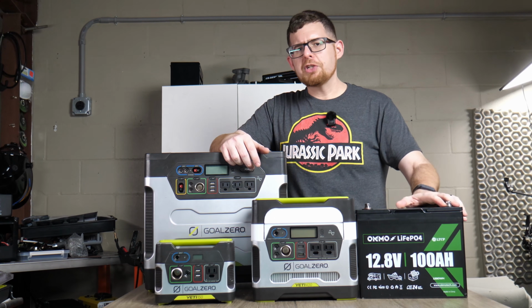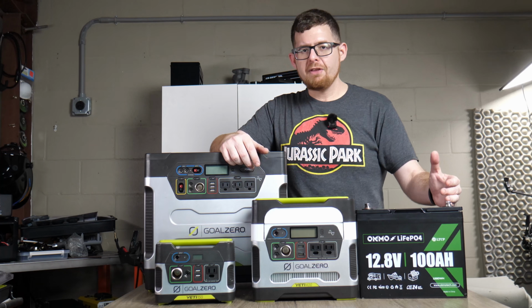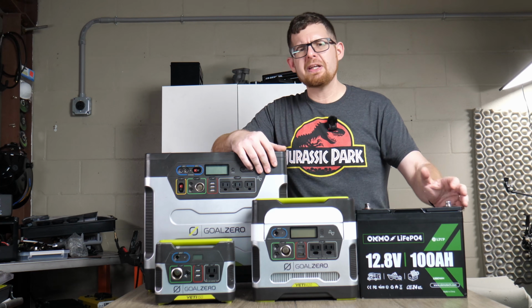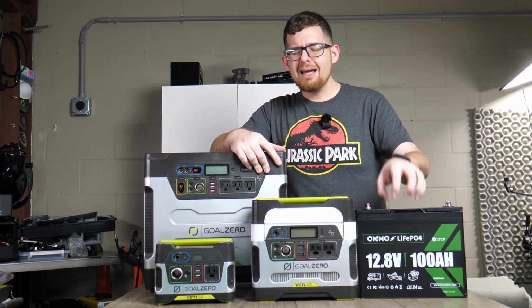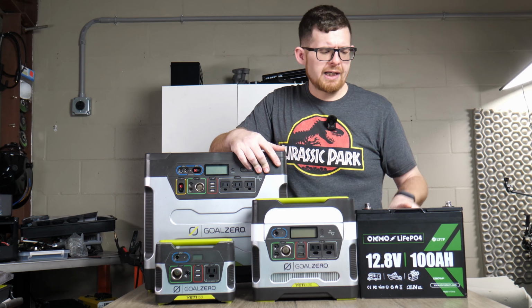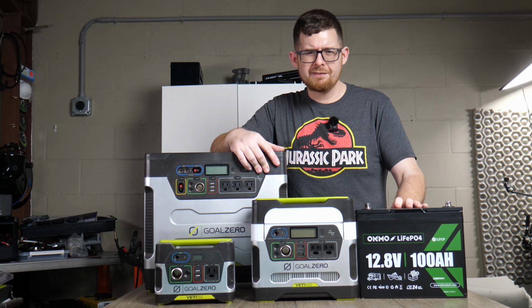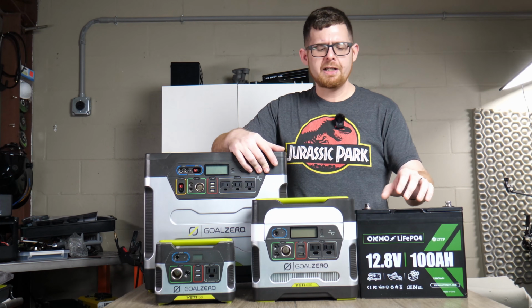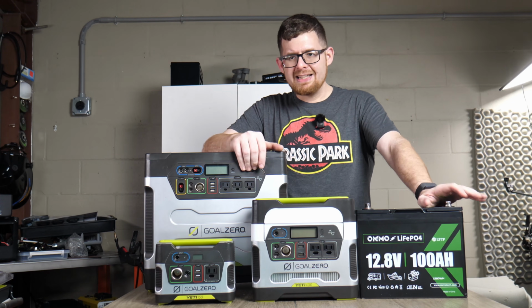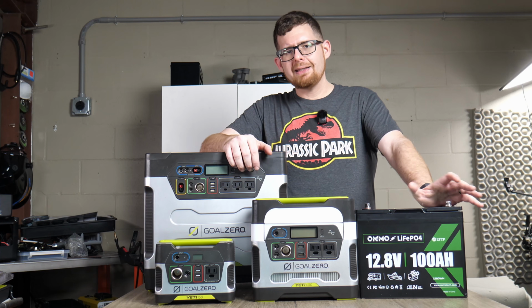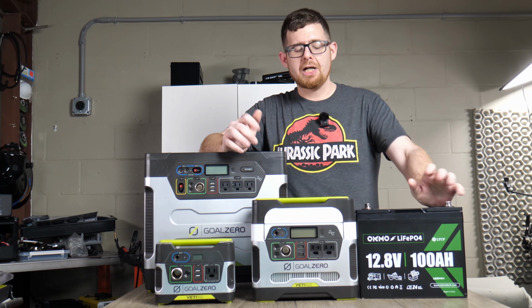But the actual voltage range on this is anywhere from 10 volts at its absolute lowest, which you generally don't want to dip down quite that low. I haven't seen where the BMS cuts this one off quite yet, I'll need to do a little bit further testing. I think it was around 10.6 volts when I did my testing, but the cells inside can go down to that level and not be completely shot.